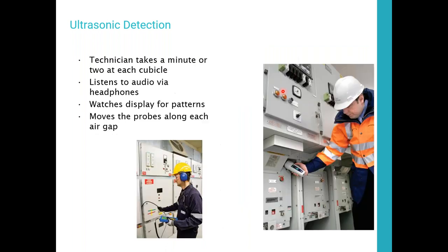You're going to go through vents and louvers of your switchgear, or using the parabolic dish, checking your overhead insulators. And you're just going to go around and listen for the PD activity. You'll get sudden changes in sound, so just a white rushing noise, almost like a wind-type sound. You may hear other rattles and noises that are happening until you get to that electrical sound that is PD, at which point you're going to slow down and try to find the highest concentration of that.